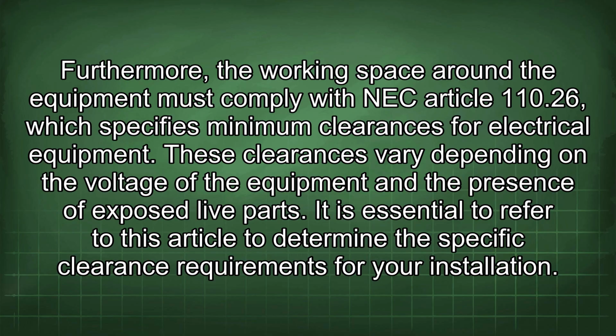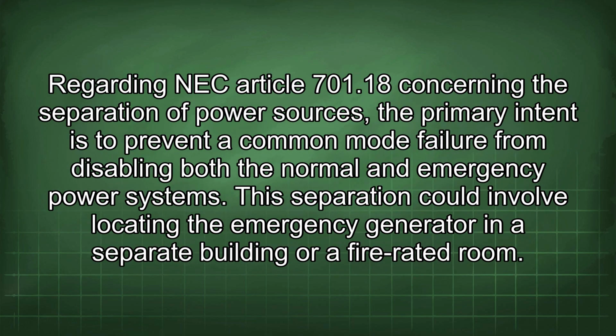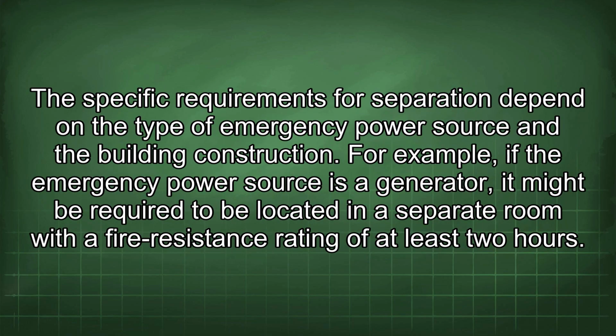It is essential to refer to this article to determine the specific clearance requirements for your installation. Regarding NEC Article 701.18 concerning the separation of power sources, the primary intent is to prevent a common mode failure from disabling both the normal and emergency power systems. This separation could involve locating the emergency generator in a separate building or a fire-rated room. The specific requirements for separation depend on the type of emergency power source and the building construction.